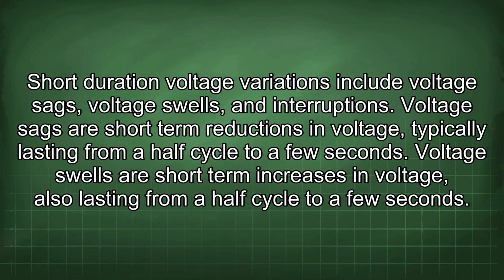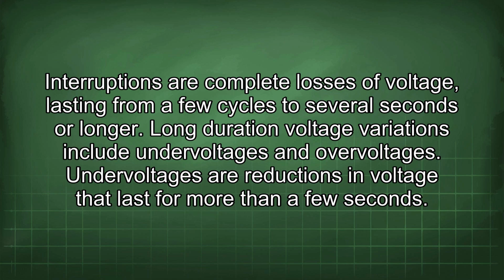Short-duration voltage variations include voltage sags, voltage swells, and interruptions. Voltage sags are short-term reductions in voltage, typically lasting from a half cycle to a few seconds. Voltage swells are short-term increases in voltage, also lasting from a half cycle to a few seconds. Interruptions are complete losses of voltage, lasting from a few cycles to several seconds or longer. Long-duration voltage variations include undervoltages and overvoltages.